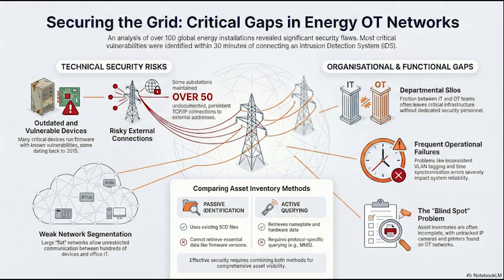Now, these are ubiquitous devices. They are what detect faults and trip circuit breakers to prevent damage. This vulnerability allows for a denial of service attack. So you can shut down the very device that's supposed to protect the grid. Yes, and you can do it with a single UDP packet. One packet, just one line of code, basically.